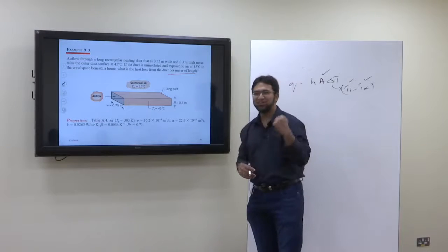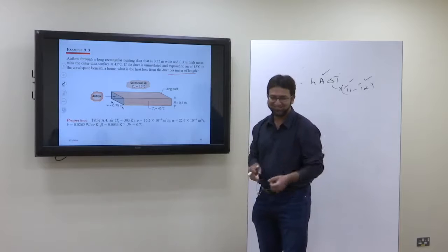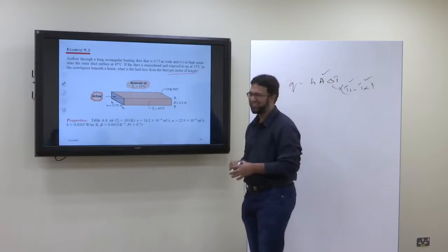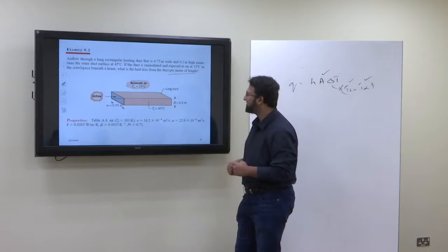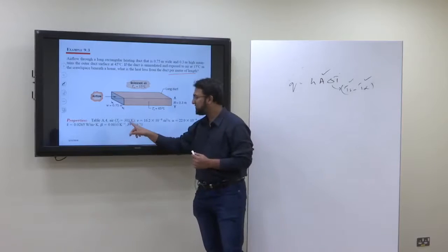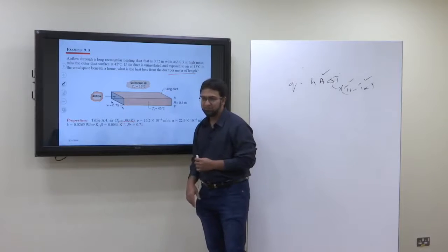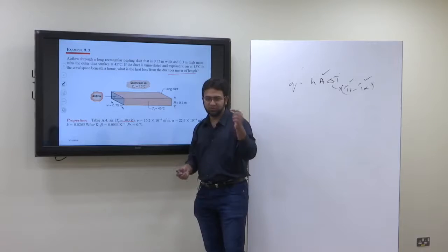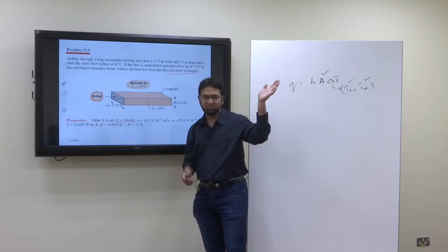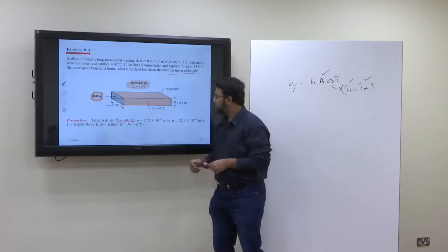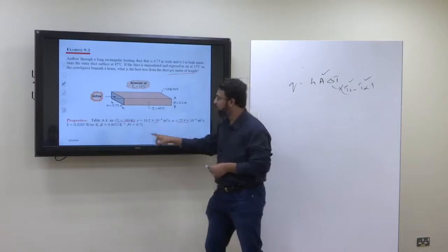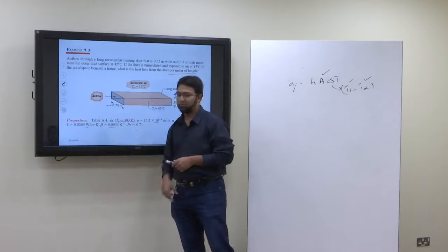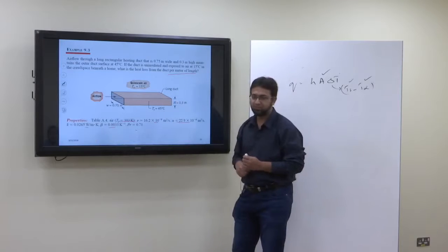Then we'll provide you the resistance of the insulation. So we will determine the mean film temperature. The mean film temperature is the average of the duct temperature and the outside temperature. And we'll find all the properties at the mean temperature.